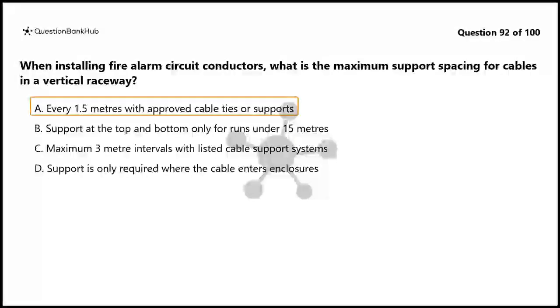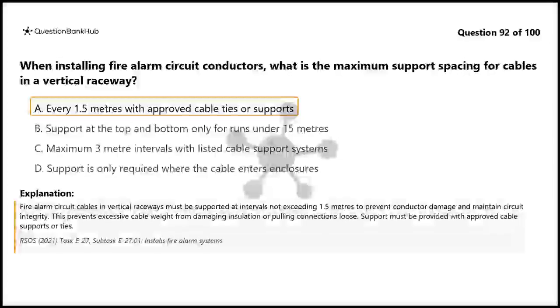The correct answer is A. Every 1.5 meters with approved cable ties or supports. Fire alarm circuit cables in vertical raceways must be supported at intervals not exceeding 1.5 meters to prevent conductor damage and maintain circuit integrity. This prevents excessive cable weight from damaging insulation or pulling connections loose. Support must be provided with approved cable supports or ties.